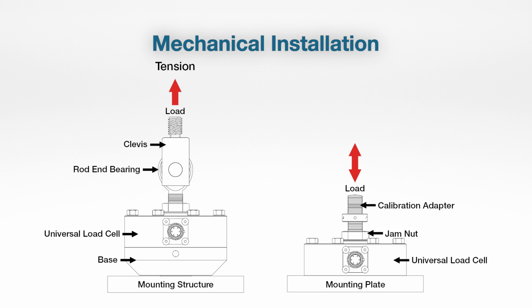In this case, you see a calibration adapter pre-installed on the load cell. That is a feature we offer. In fact, if you look at our calibration grade sensors on our website, you're going to see that they all come with these. Well, why do they come with them? Well, like I mentioned earlier, we recommend preloading. And it's often easier for customers to go with a calibration adapter where we'll preload it here at the factory and calibrate it that way so that you'll be able to attach on the calibration adapter end and have good results moving forward that way.